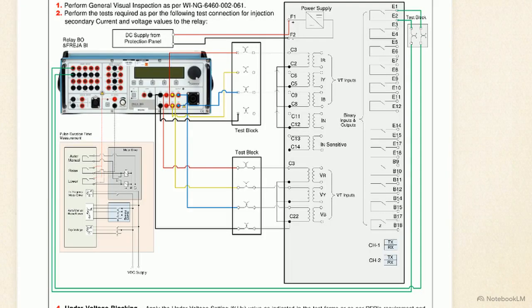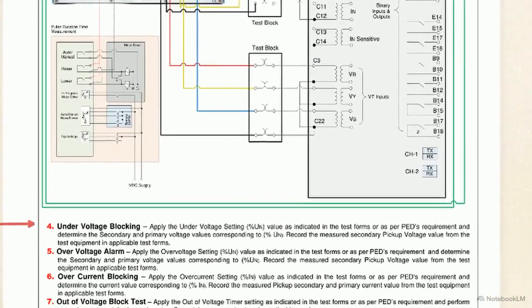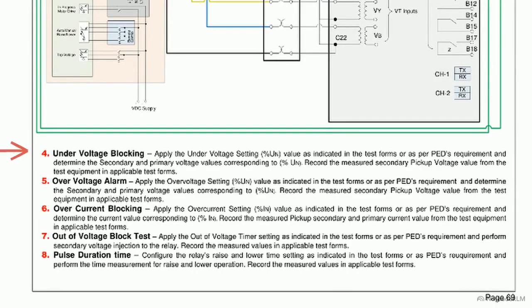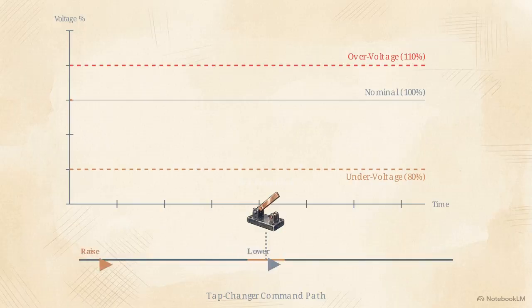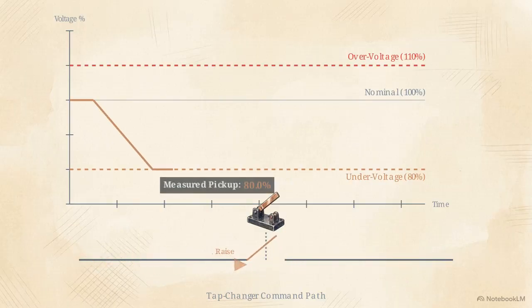The third module validates the blocking protection functions. This schematic details the required injection kit connections to the binary inputs. First, inject dropping secondary voltages to simulate a grid sag and trigger the under-voltage block. You must record the exact percentage pickup value at the precise moment the relay physically blocks the raise and lower tap commands. Next, inject excess voltage to cross the upper limit, confirming it triggers the overvoltage alarm.